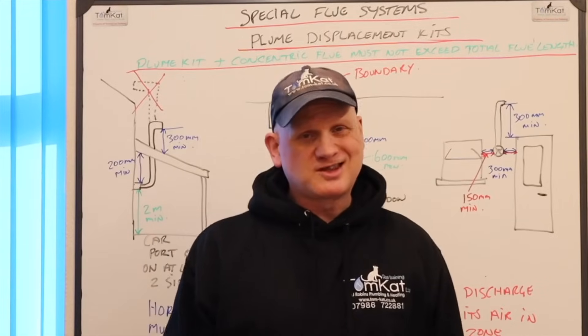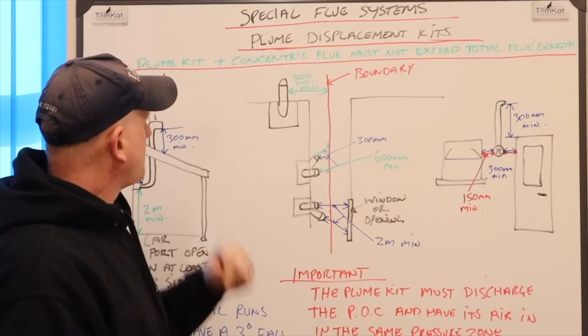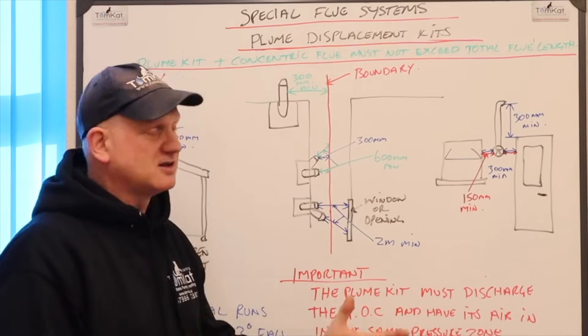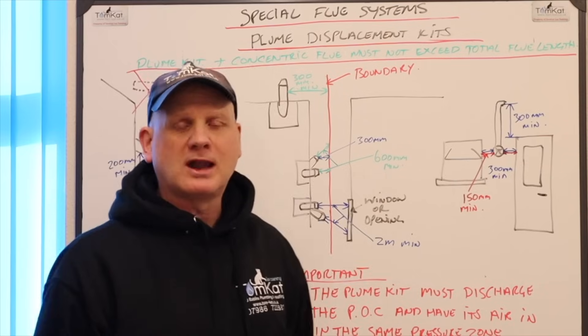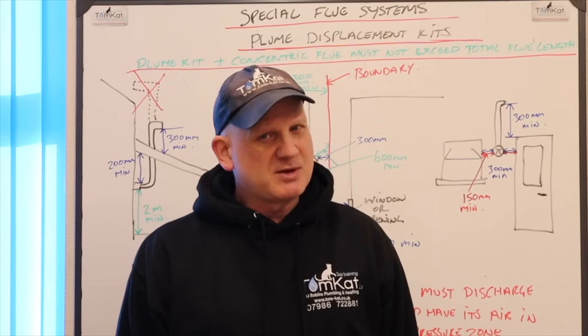Another important flue consideration is what I've put here in green. So, the plume kit plus the concentric flue system, so the standard flue system, must not exceed the total length of the flue system designed for that boiler. So, there might have been a bit of maths involved.